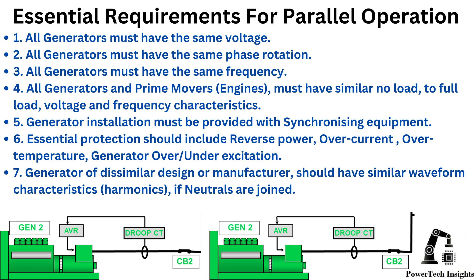1. All generators must have the same voltage. 2. All generators must have the same phase rotation. 3. All generators must have the same frequency. 4. All generators and prime movers (engines) must have similar no-load to full-load voltage and frequency characteristics.